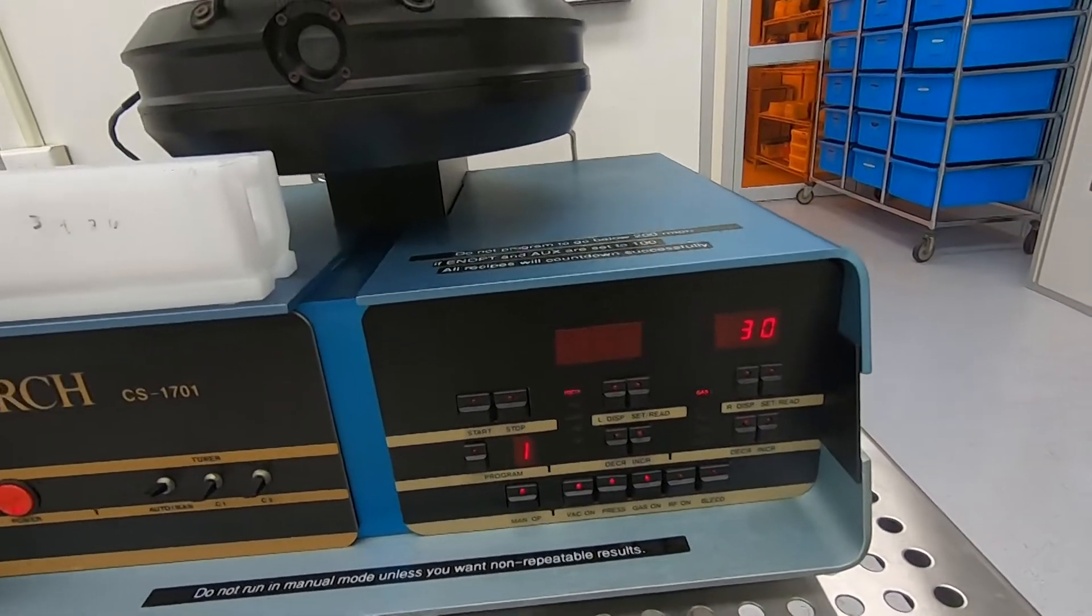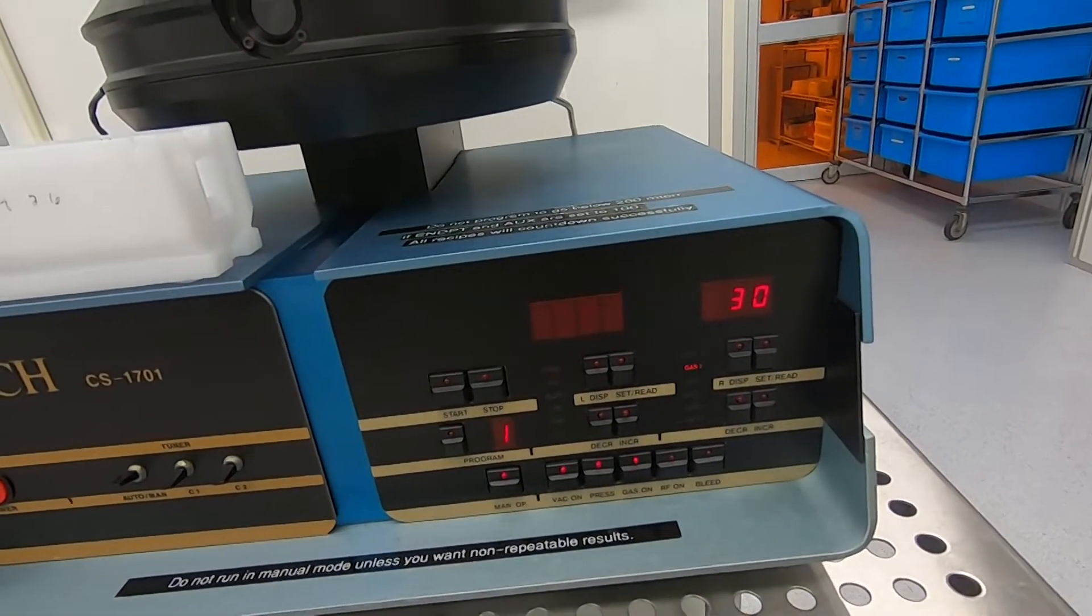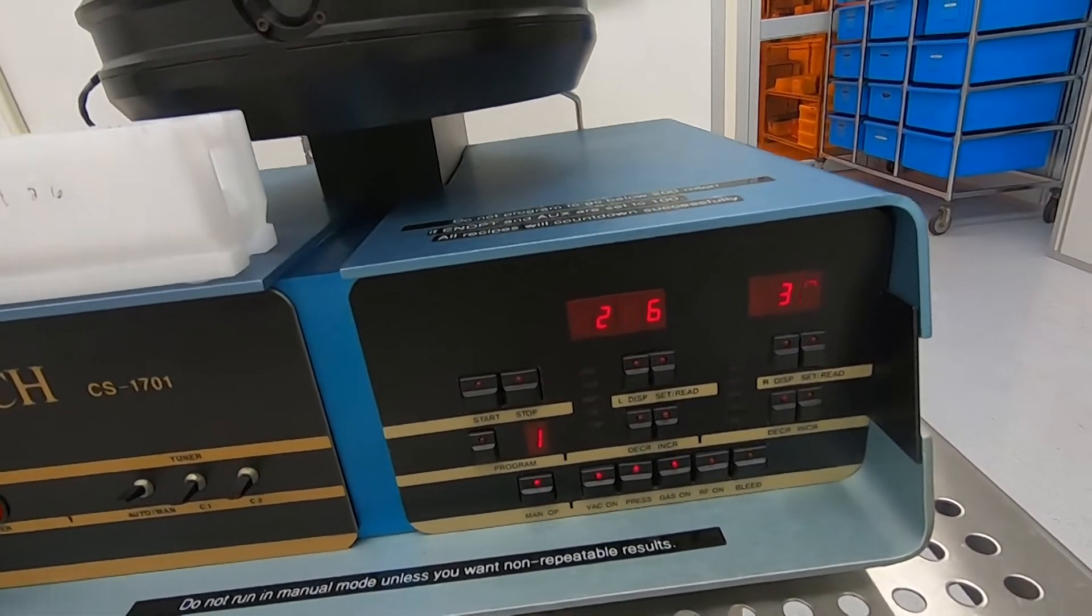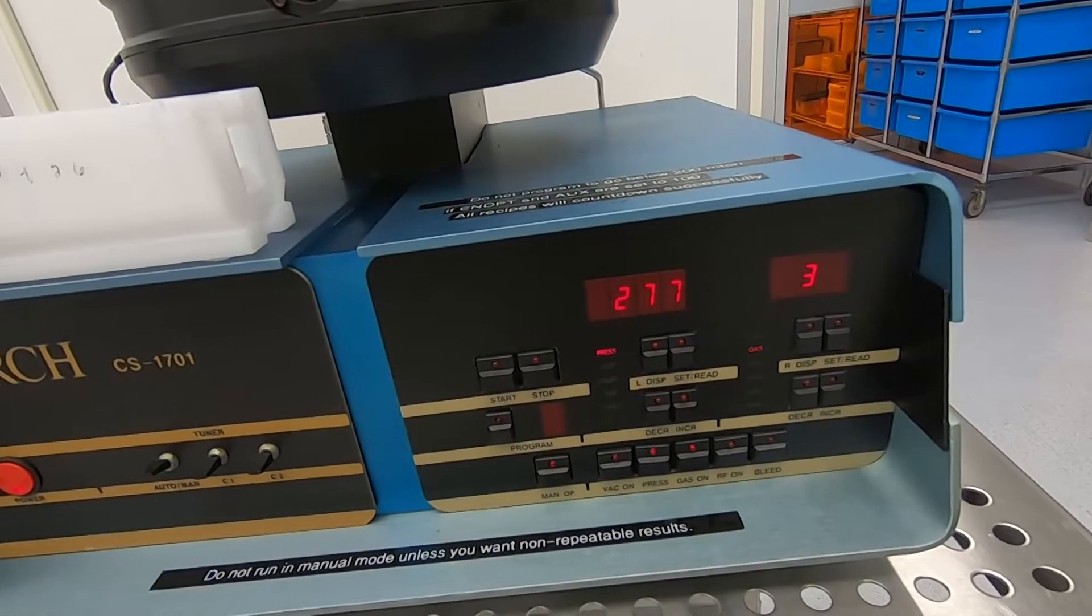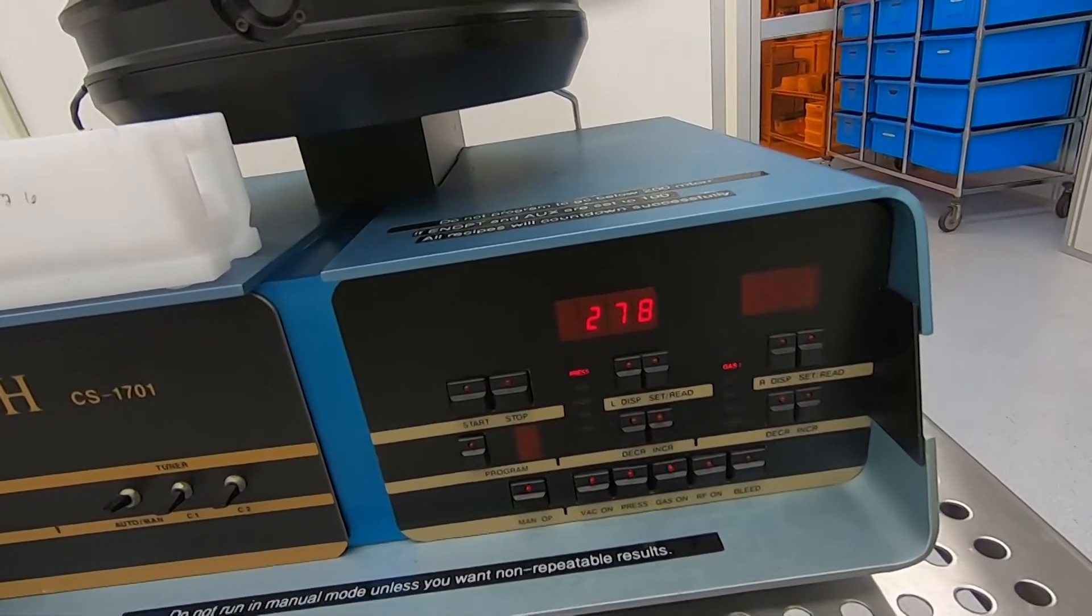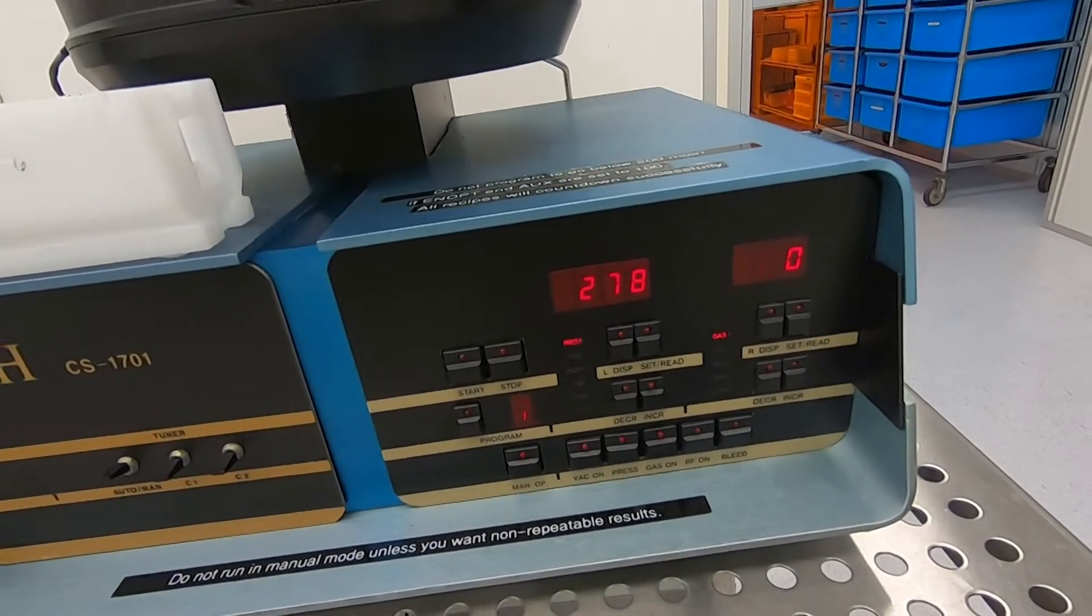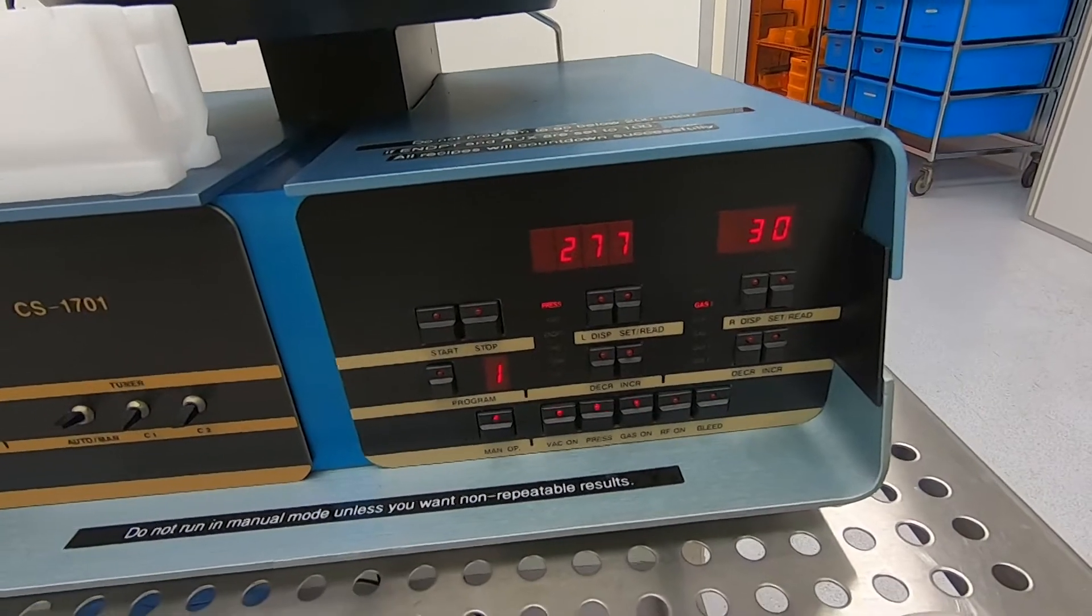Actual pressure, we want it to be about 300 millitorr, and we're going to do 300 watts for, I don't know, five minutes. We want to make sure those wafers are clean.